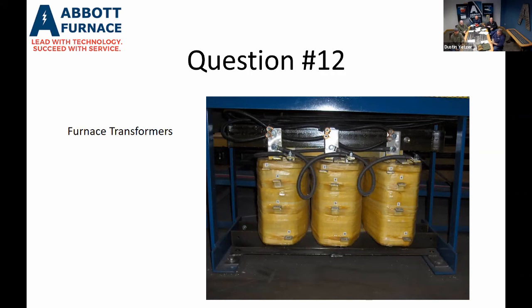Okay, changing taps on a transformer. The first thing that you need to determine is what the zone is doing as far as the load goes. So the first thing you want to look at is your voltage and your current that zone is pulling. You definitely want to have an electrician look at this. You can use the amp meters that are on some of the older furnaces, digital or analog amp meters. Some of the newer furnaces, or the furnaces that have been retrofitted to a newer SCR package, have a readout of what the SCR reads, and you can get the load voltage and amperages off of that.